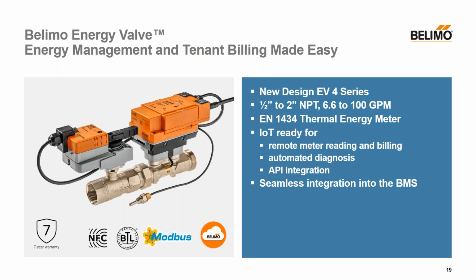The EV4 accurately measures, controls, and monitors fluid velocity and energy consumption, and is IoT ready for remote meter reading, billing and automated diagnosis, and API integration. Also new with the EV4 is Power over Ethernet, or PoE. This capability enables one standard Ethernet cable to provide both power and data transmission, greatly simplifying installation. It also allows seamless integration into the BMS using BACnet IP or MSTP, Modbus TCP or RTU. These also come with a digital calibration certificate that can be printed out on demand and contain the Delta T Manager and glycol monitoring and compensation technology for optimum performance.